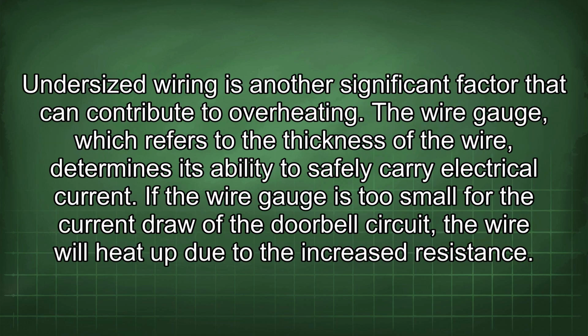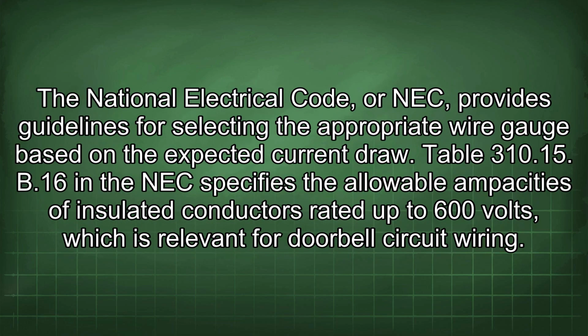Undersized wiring is another significant factor that can contribute to overheating. The wire gauge, which refers to the thickness of a wire, determines its ability to safely carry electrical current. If the wire gauge is too small for the current draw of the doorbell circuit, the wire will heat up due to the increased resistance. The National Electrical Code, or NEC, provides guidelines for selecting the appropriate wire gauge based on the expected current draw. Table 310.15(B)(16) in the NEC specifies the allowable ampacities of insulated conductors rated up to 600 volts, which is relevant for doorbell circuit wiring.